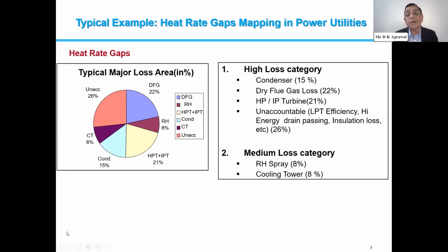And of course, there are many unaccountables, like high energy drains, insulations. The LP turbine efficiency is also a very big factor, which we are not able to measure because of the moisture content in the last stages of the turbine blades. And then of course, as has been shown by Tata, there is the RH spray, and of course the cooling tower. The cooling tower is a very, very important area from the point of view that these are some very low hanging fruits. We can definitely improve the performance without making much effort, because these are all visible things at the cooling tower side. Next slide, please.